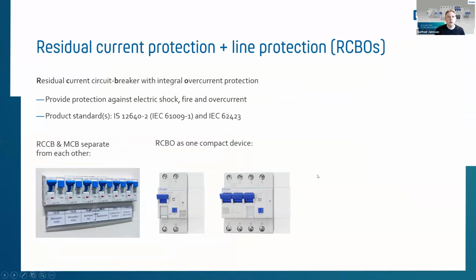That was RCCBs. Coming to RCBOs, which is a kind of combination of residual current circuit breaker with integral overcurrent protection. That means line protection. So it's a combination of both. Again, to provide protection against electric shock, fire, but as well overcurrent. And the main purpose is to save space.